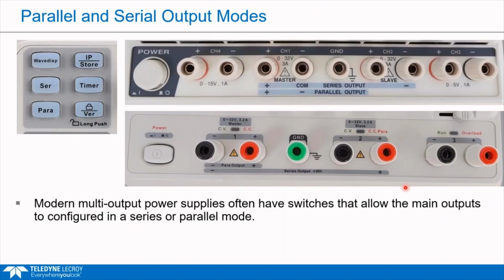Next would be parallel and serial output modes. Depending on the power supply series, you'll have a guide on the bottom of the terminals saying what the connection is for parallel and what it is for series. You've got parallel and series switches here, and on different power supplies they're labeled slightly differently, but they all do the same thing. If I press series, my series output would be from the black through to the red - meaning this red and black are joined together internally. If I set the parallel button, I've got parallel on these two terminals, so I'll get twice the current out. You can't press both at the same time - it won't accept that.